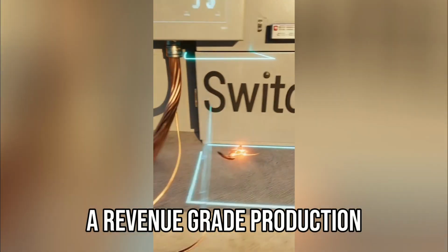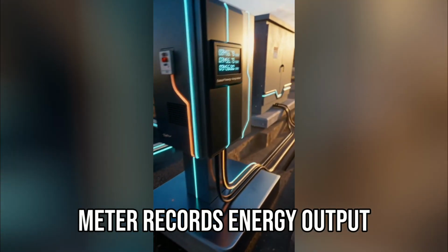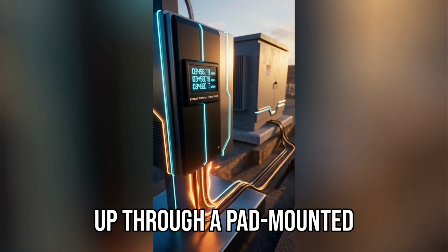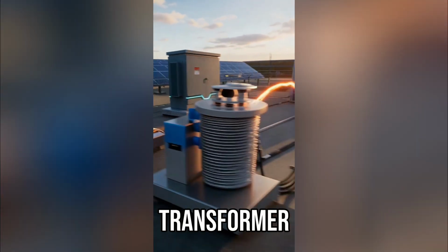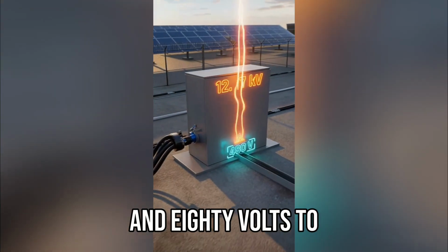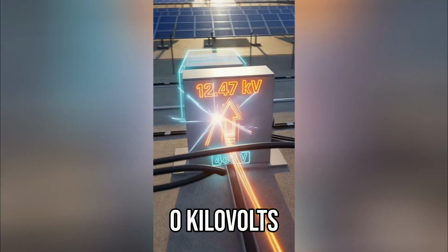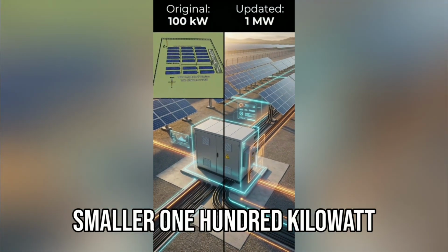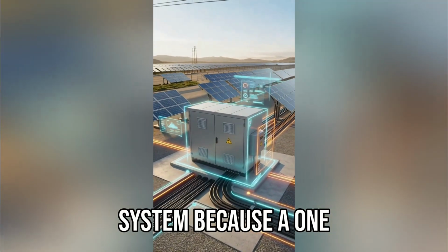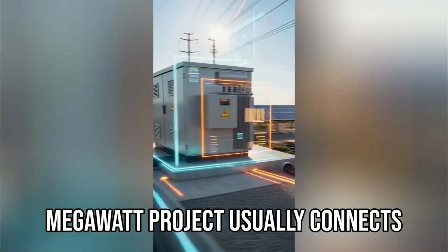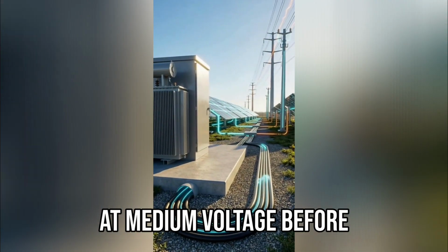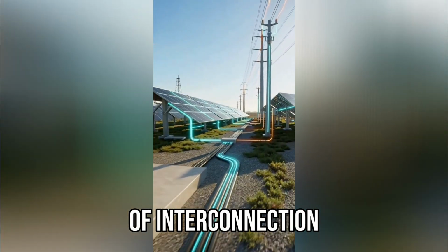A revenue-grade production meter records energy output before the system steps up through a pad-mounted transformer, typically from 480 volts to 12.47 or 13.80 kilovolts. That transformer is a key difference from the smaller 100 kilowatt system because a 1 megawatt project usually connects at medium voltage before reaching the utility point of interconnection.